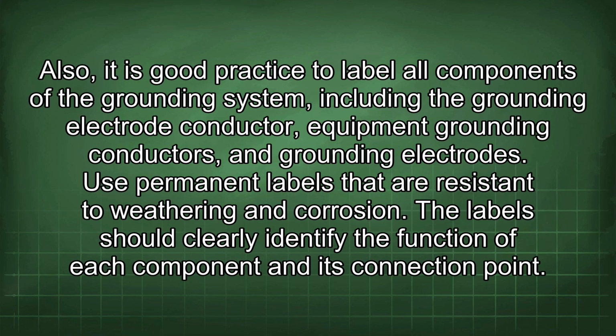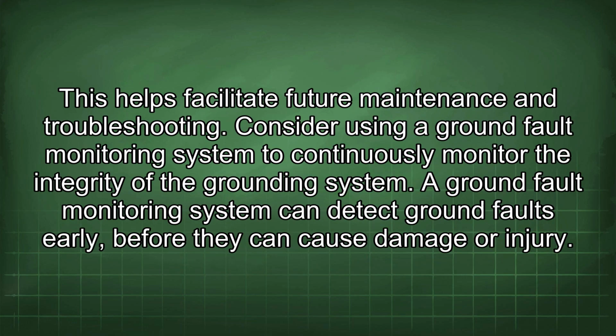Also, it is good practice to label all components of the grounding system, including the grounding electrode conductor, equipment grounding conductors, and grounding electrodes. Use permanent labels that are resistant to weathering and corrosion. The label should clearly identify the function of each component and its connection point. This helps facilitate future maintenance and troubleshooting.